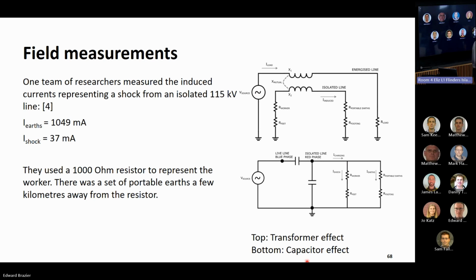A team of researchers in America measured this effect in the field. They looked at two transmission lines in parallel, one in service at 115 kV and the other isolated. A few kilometres away they connected portable earths to the foot of the tower, and further away still, a resistor representing roughly the resistance of a person. They found a bit over an amp flowed through the portable earths, and 37 milliamps still flowed through the resistor representing a worker. That 37 milliamps represents the shock current that would go through the worker if they touch the isolated line, earthed just a few kilometres away.